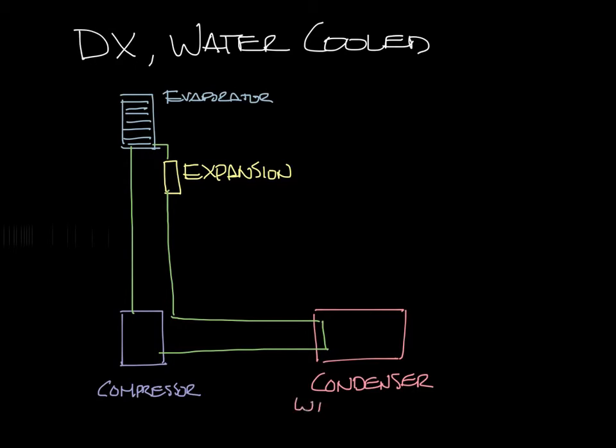But the condenser is water-cooled. Water flows through a water-cooled condenser, and the heat transfer happens between the refrigerant and the water. In our water-cooled condenser, the water enters the tubes cool. As the refrigerant vapor flows past the tubes, heat is transferred from the refrigerant to the water so that the water exits the condenser warm, and the refrigerant leaves as a liquid.